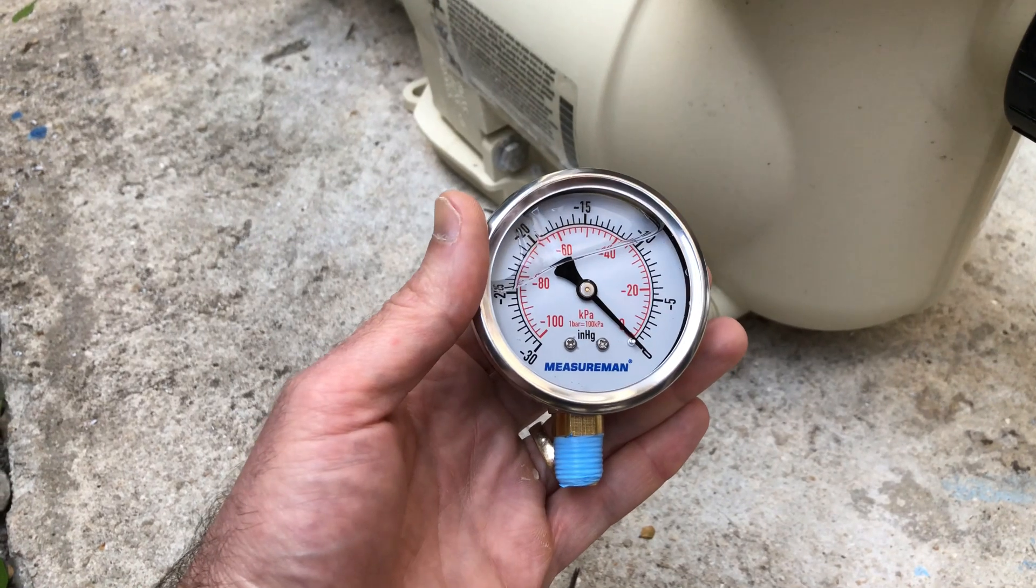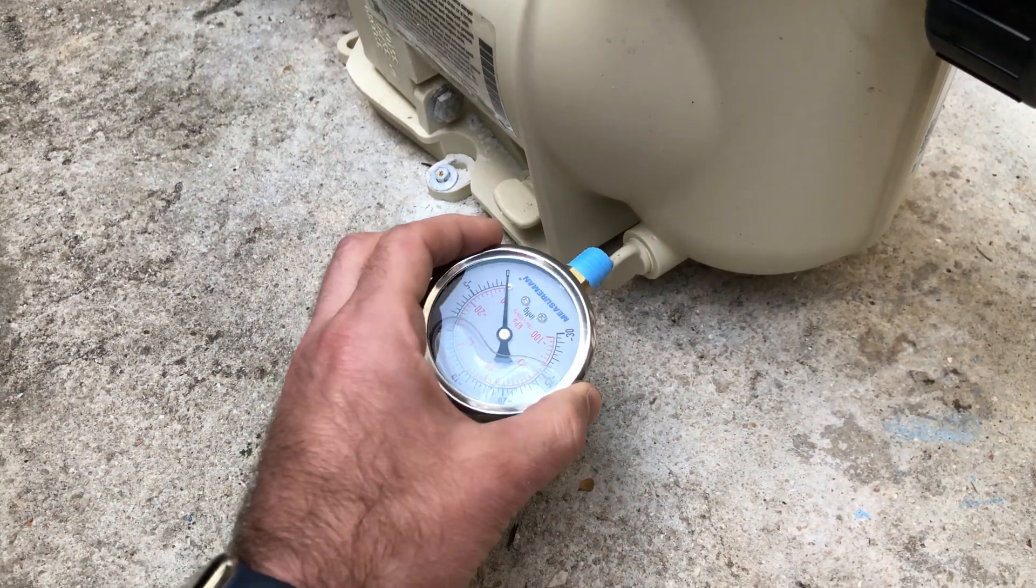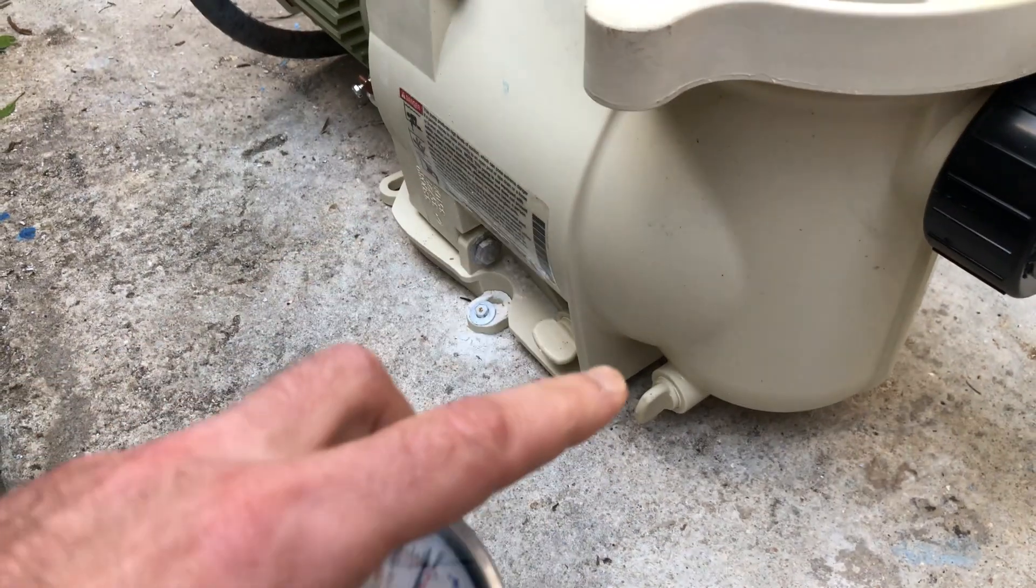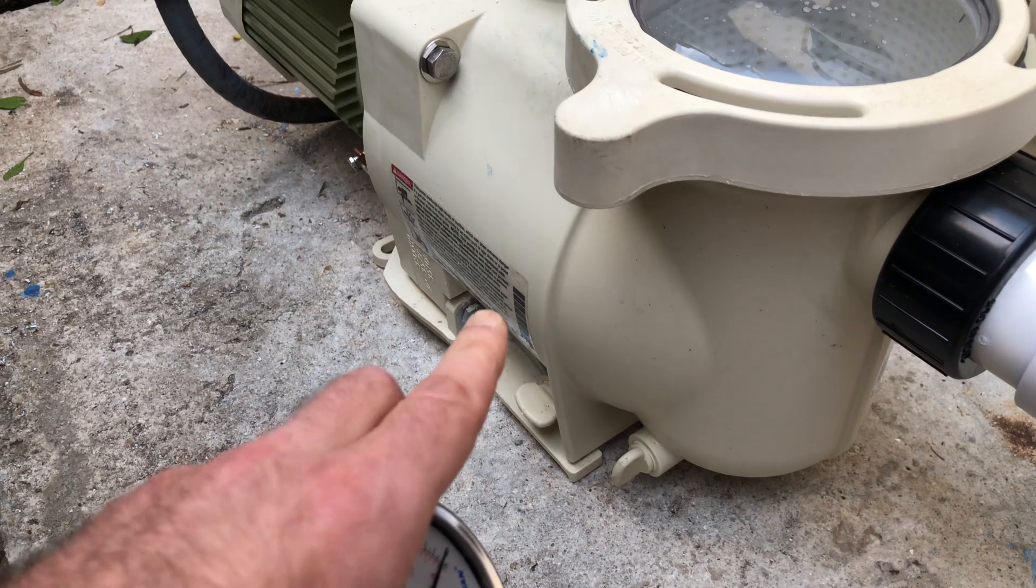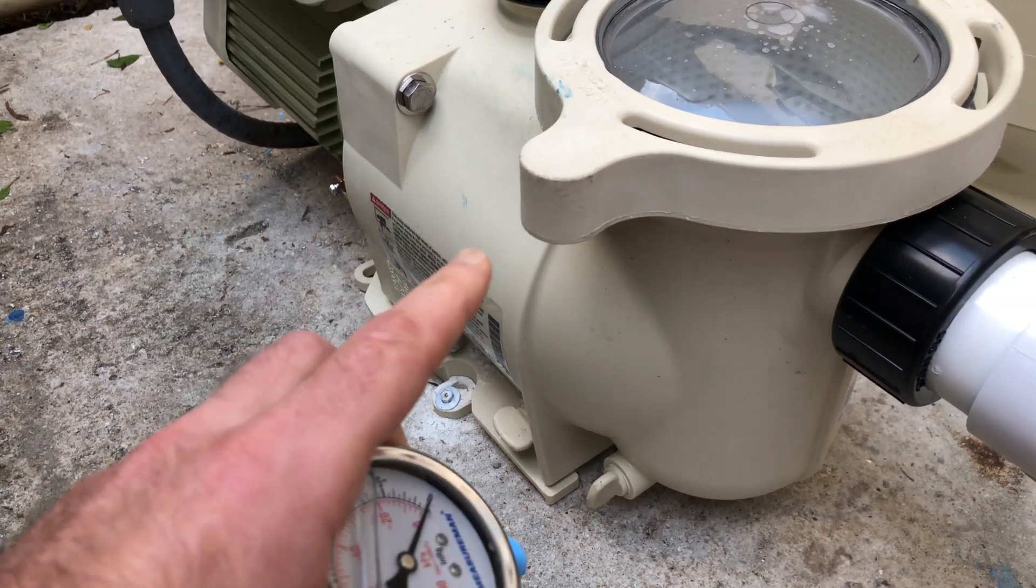So I'm going to go ahead and screw this Measure Man vacuum gauge into the suction side of the pool pump here, and then using the power of math, I'm going to be able to figure out my total dynamic head, and then I'm going to show you how to use the Pentair performance chart to figure out the gallons per minute through the system depending on the RPMs that you have it set to, crossed with your total dynamic head in the system.